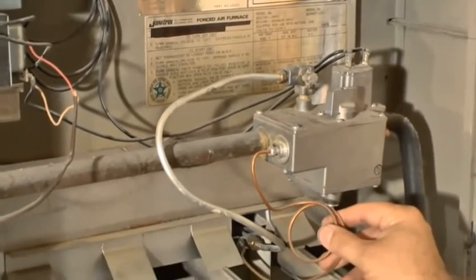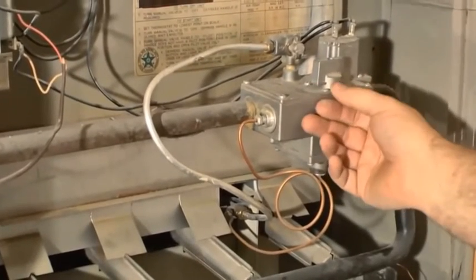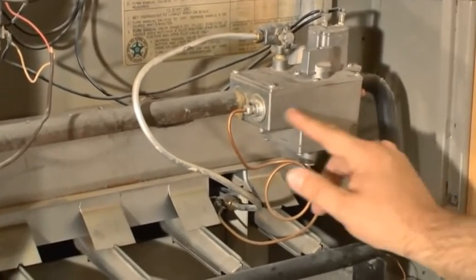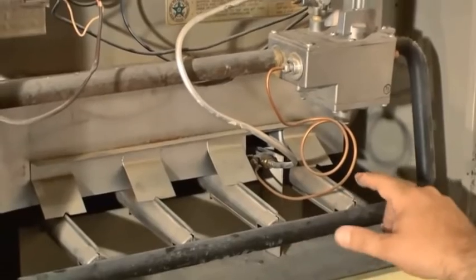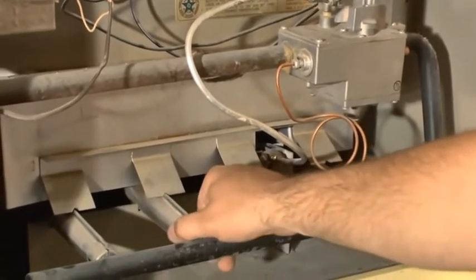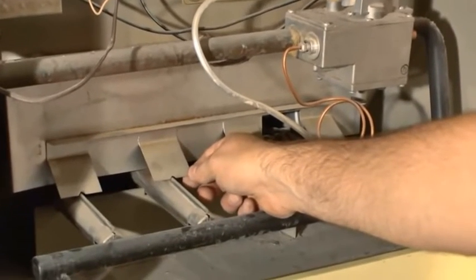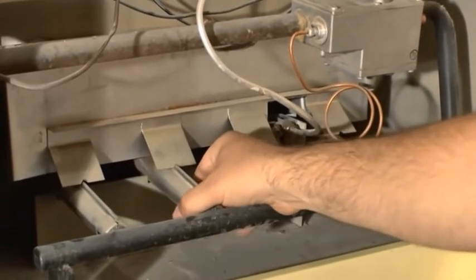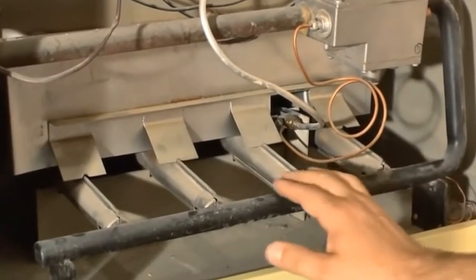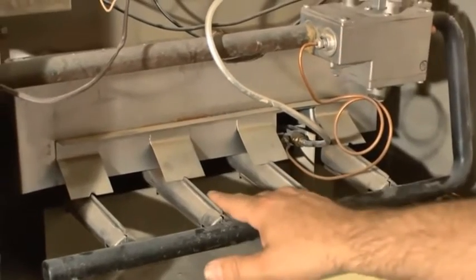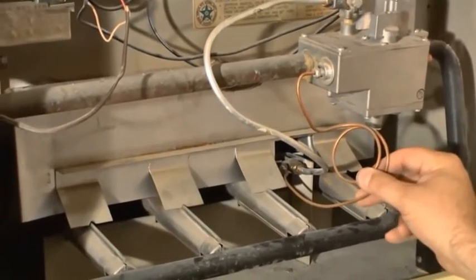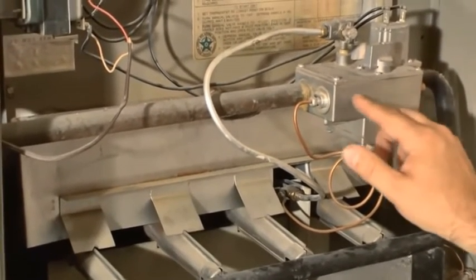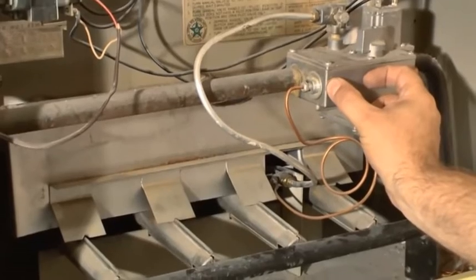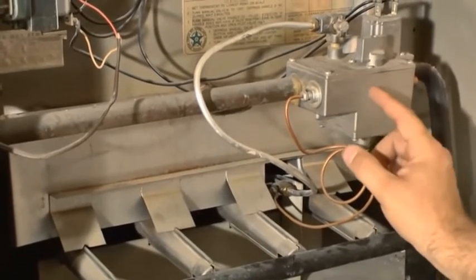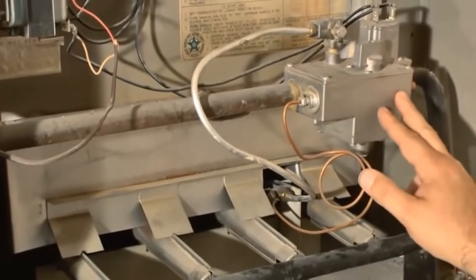There, I just shut the gas off to the pilot. Once the pilot's out, if the thermocouple cools down, then this valve shuts off and will not let gas go to the manifold here. This has 4 burners. These are actually monoport burners. They're some of the first monoport style burners that I've seen. They actually shoot a flame into the heat exchanger. That click was the thermocouple. It had cooled down enough to where this electromagnet let go and shut the gas off for the whole gas valve. So now there's no way for gas to get through the gas valve.